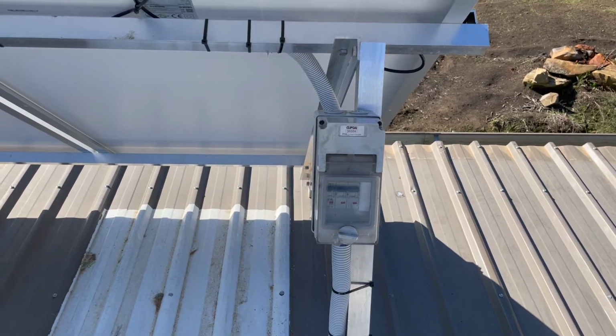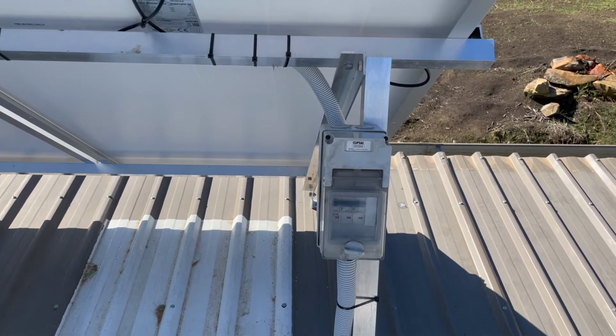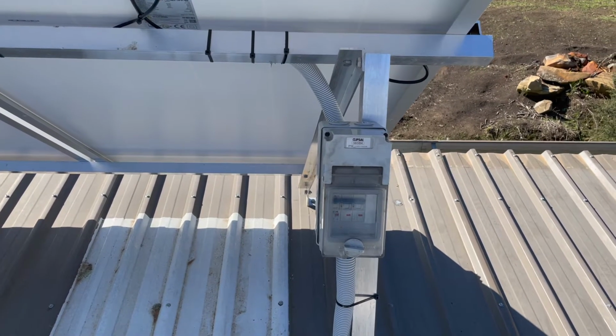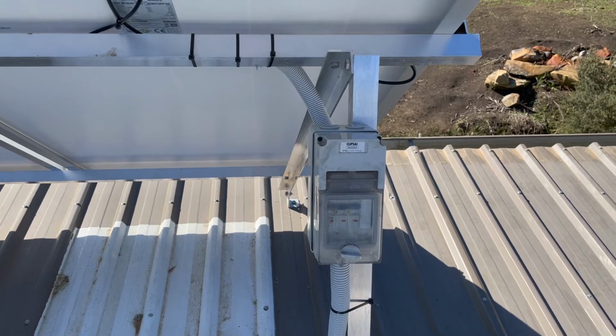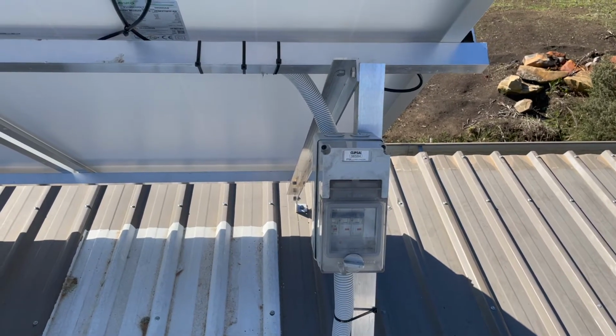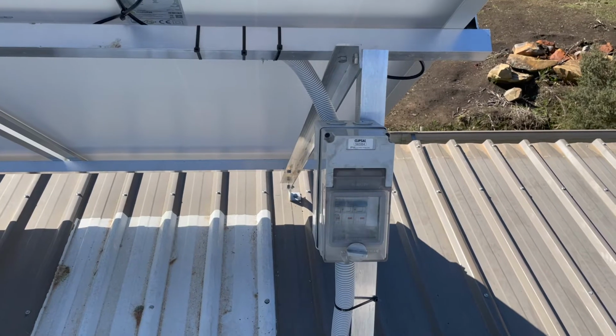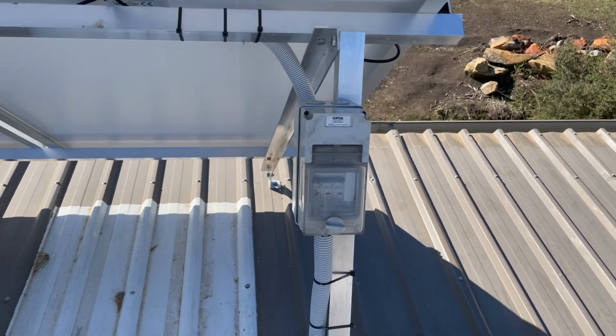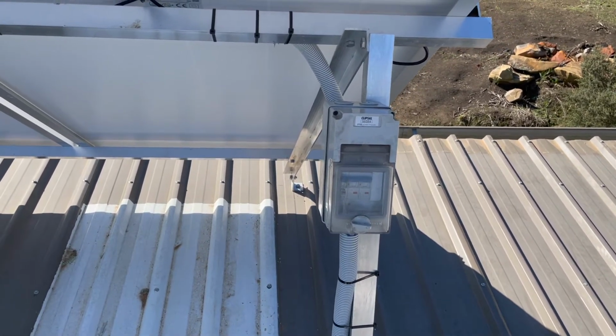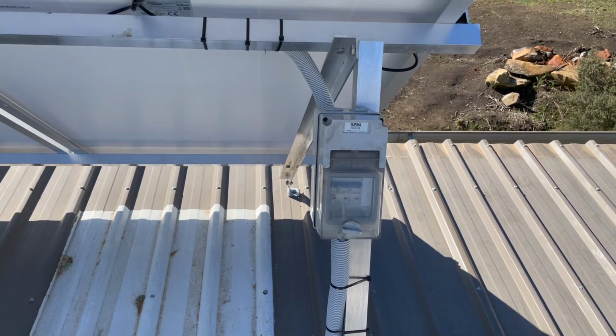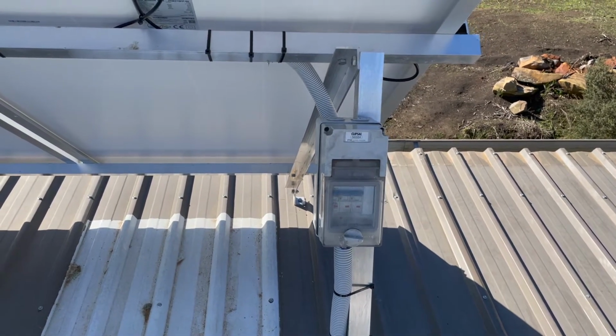You should note, 20-30 years ago, when we used to put these arrays in, there was no such thing as a solar array disconnect. We used to just put a junction box here and hardwire everything all the way through to the power board. It's better to have a disconnect on the roof, and rather than using circuit breakers, which I've done, you'd be better off buying a dedicated solar array disconnect switch.